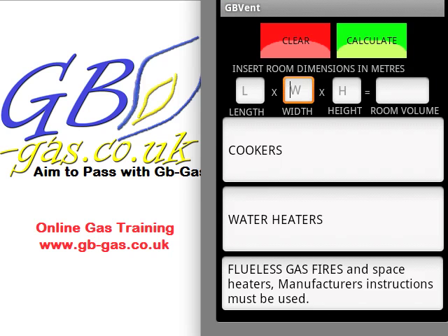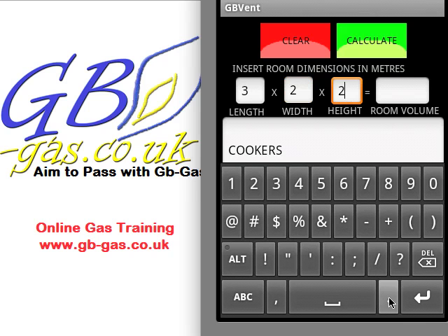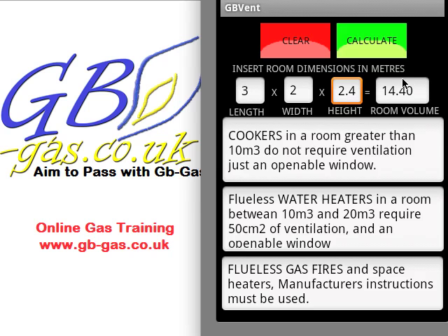The main information we need for flueless appliances is the room length, width, and height — we need to find the room volume in metres cubed. So we insert the length, which could be 3 metres, the width let's make 2 metres, and the height, an average height, is 2.4 metres. We then press calculate, and this gives us our room volume — in this case 14.4 metres cubed. So a cooker in this room, as long as it's greater than 10 metres cubed, does not require ventilation, but it does require an openable window.